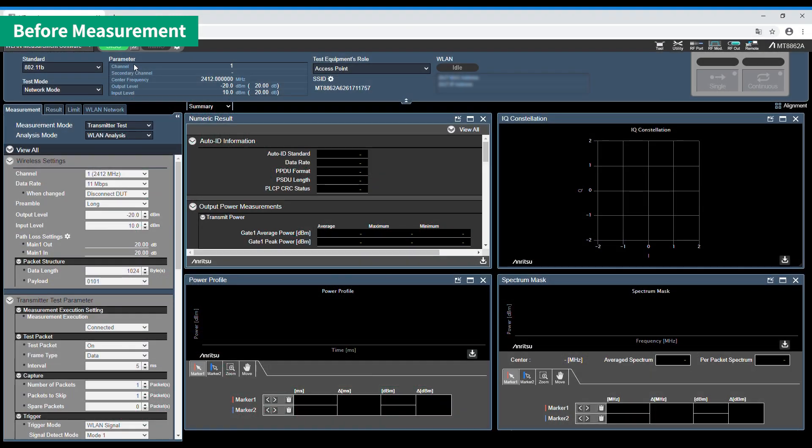Three operations are required to connect the PC and MT8862A. First, connect an Ethernet cable between them. Next, set the PC IP address to 192.168.20.10. Last, input 192.168.20.100 at the PC web browser URL.